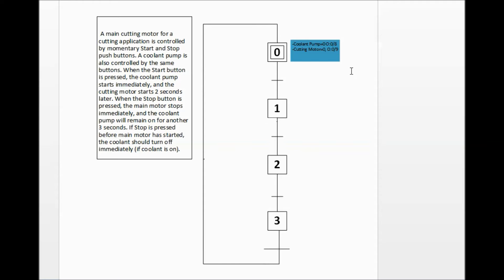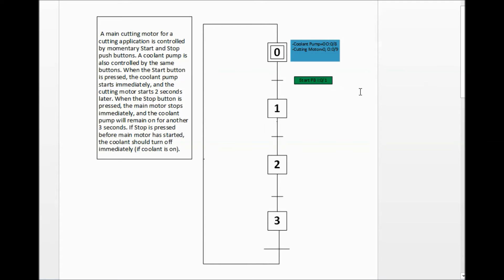In order for anything else to happen we need a transition. Going back to our control process: when the start button is pressed, the coolant pump starts immediately and the cutting motor starts two seconds later. So we have a transition — we must wait for the start button before turning on the coolant pump. I've added the transition: start PB (start push button) located at I:0/1 must be true in order to move to step 1.